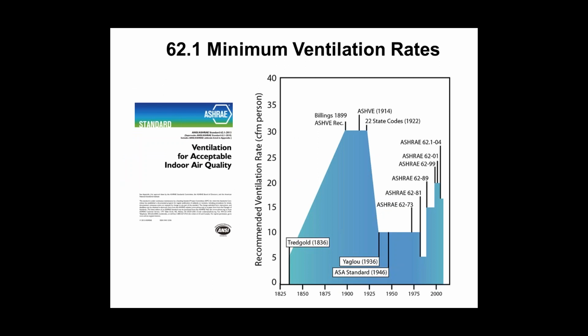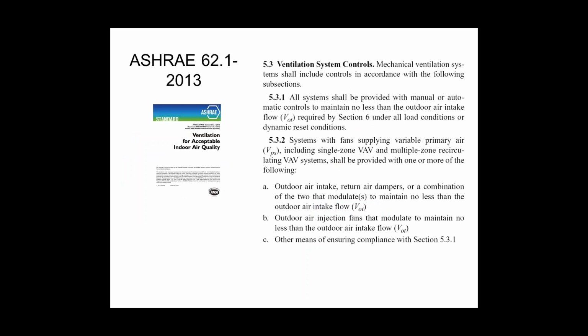You guys know we have ventilation codes. You know we've had them for a long time. They used to be based on a per person basis. As of 2004, ASHRAE Standard 62 Addendum N, we switched it from a per person basis to a per person and a square foot basis. And the main reason for that was to allow us to ventilate differently for people versus spaces, right? The two reasons we ventilate a space are people. People basically stink and they bring germs in the building with them, and you need to dilute them down. And then the building itself, the paint, the furnishings, the carpeting, whatever, is giving off VOCs, and we need to dilute those down. So now, as of 2004, we're allowed to take care of the people-based and the space-based pollutants separately with the ventilation rates.